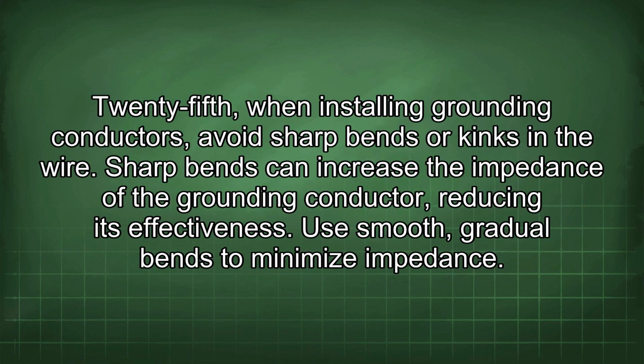25th, when installing grounding conductors, avoid sharp bends or kinks in the wire. Sharp bends can increase the impedance of the grounding conductor, reducing its effectiveness. Use smooth, gradual bends to minimize impedance.